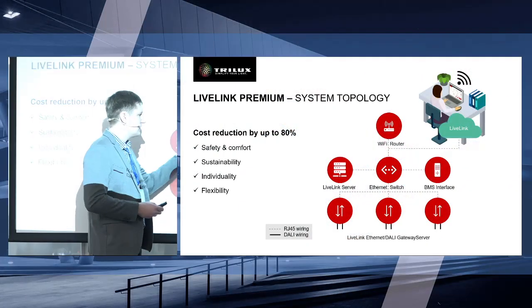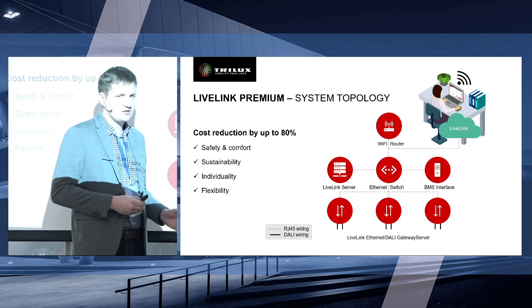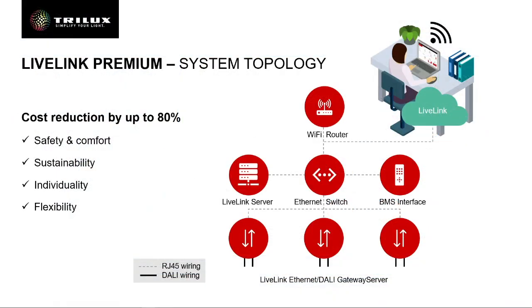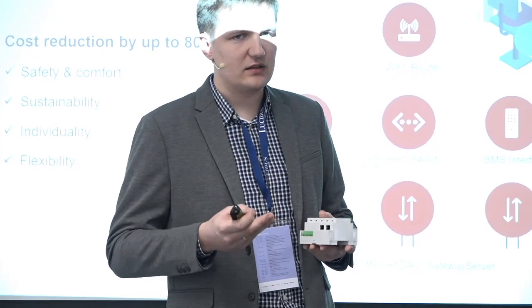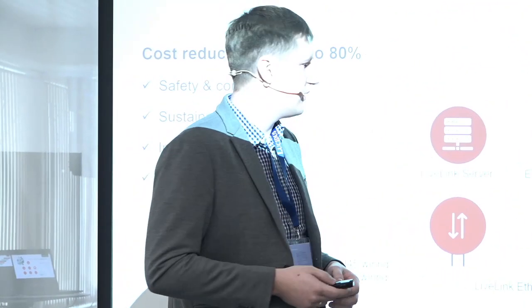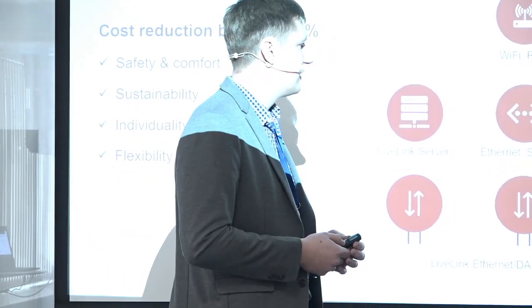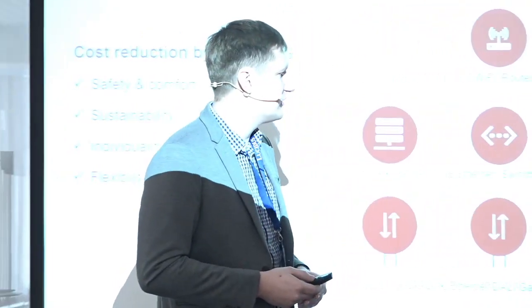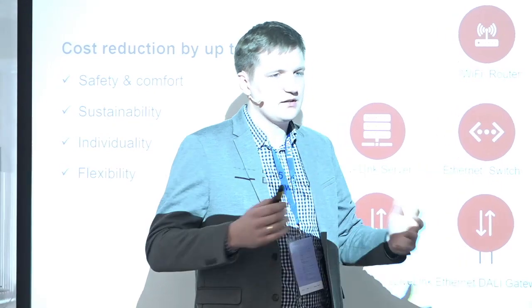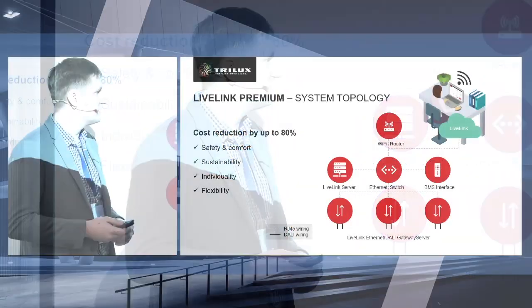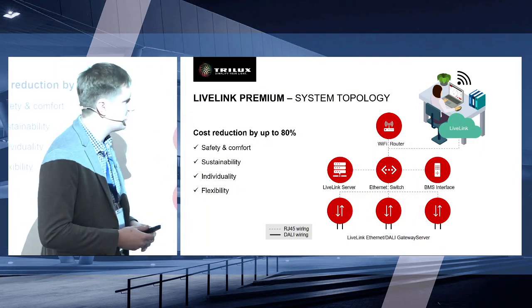The rest of the Ethernet topology is between the Ethernet switch, so it's standard LAN wiring, to the DALI gateways. DALI gateways are devices which communicate between the server, which is the head of the system, and the luminaires. Because luminaires have to be controlled by DALI2 communication, this is somehow like a translation between the LAN connection and the DALI connection. There's also the possibility to connect to the BMS interface, to Wi-Fi routers where we can share the wireless network to control the whole system, and connect to the LiveLink cloud system, which I'll explain later.